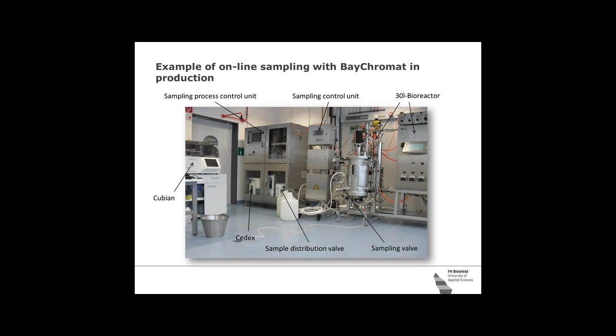This is the distribution valve or the distribution unit. The sample sometimes needs to be transported over a distance of 20-25 meters from the bioreactor or from the sampling unit to this analytical unit, because they may be some meters away, or the customer may want to connect more than one stainless steel bioreactor to this device because it's very expensive. And to somehow reduce costs, it may be worth connecting more than one bioreactor. But then, of course, you run into issues with cross-contamination because there's one valve here in the middle, as you can see in this image, that connects different bioreactors, and that may not be so beneficial in pharmaceutical processes.